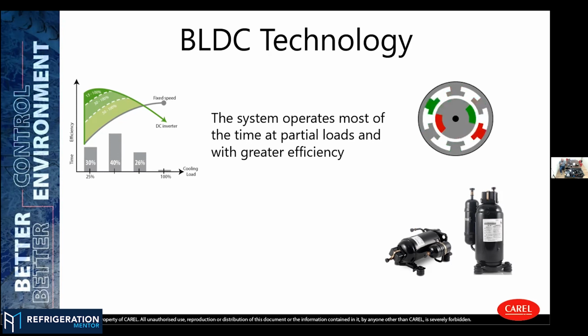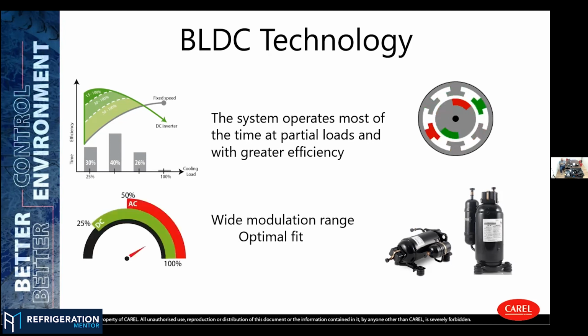So we need the inverter. And since we have the inverter, we can modulate the speed of this compressor. BLDC technology is well known because we can have a very wide range of operation. With traditional motors, when you have a compressor and an inverter driving this AC motor, you have some limitations on the modulation, mainly because of the lubrication of the moving parts inside the compressor.